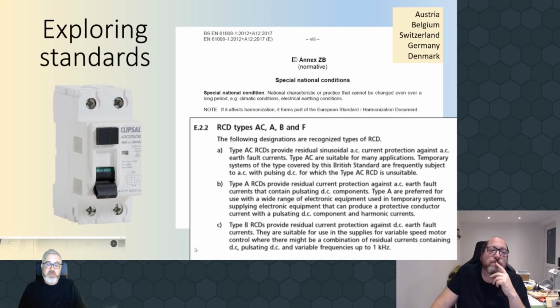One of the key things I always remember is on the railways, when they go to test the RCDs, they will test them at night time when the trains aren't running and everything's switched off. But during the day, when you've got dozens of amps of DC straight current leaking into the system, that's when the performance of the device will be compromised. But it's not tested then.